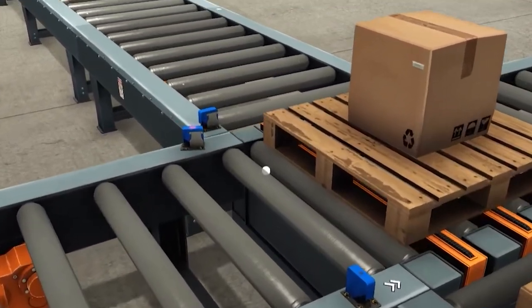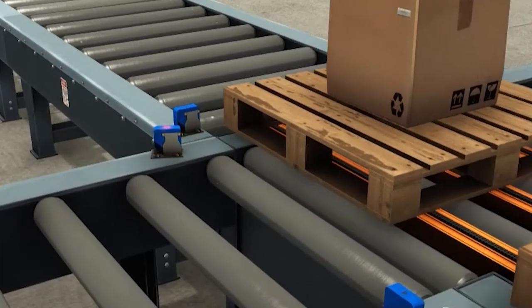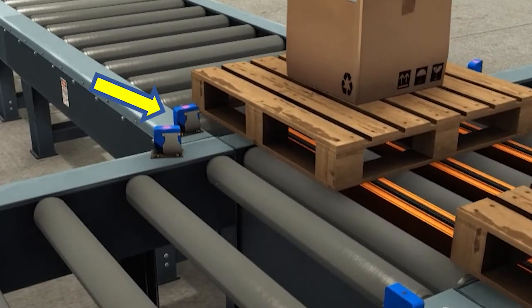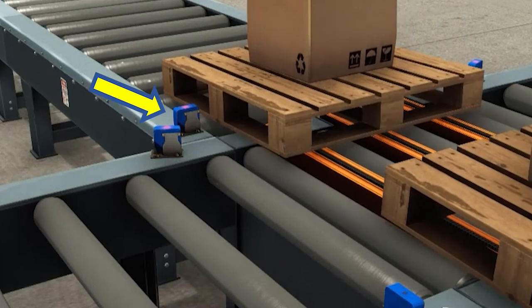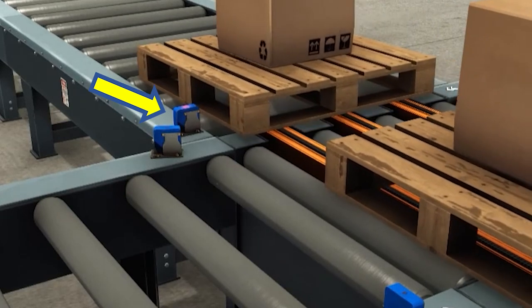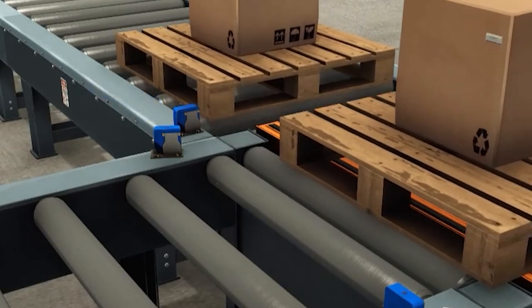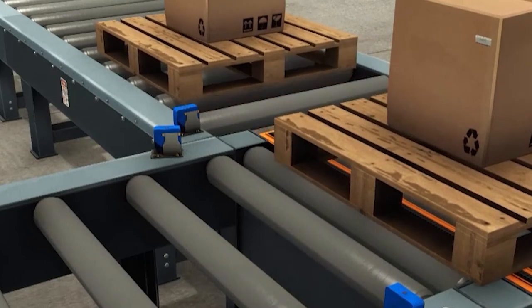The problem is that the first pallet clears the transfer unit as it passes this photo eye, indicating that the pallet is clear. But because the trailing pallet has already entered the transfer unit's envelope, it is being lowered onto the rollers instead of being allowed to continue through.